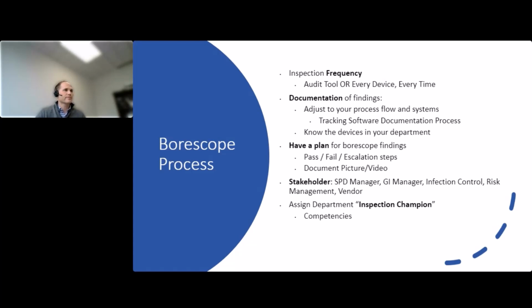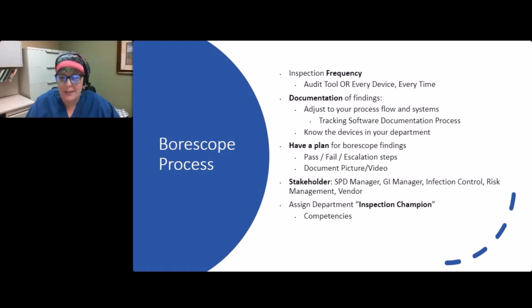So we do it kind of two different ways. And again, there's so many ways that you can develop your own internal process. It's not that it has to be X and has to be Y. So the first way that we do it is we use it as part of our standard documentation when we're reprocessing an endoscope, that it has passed its verification of the manual clean. So I know on every scope that we reprocess, and we use our instrument tracking system, Censis, we're very elevated with integration into that. So they mark, did it pass its residual protein test?